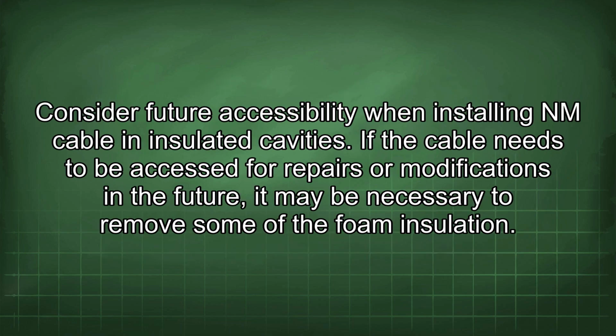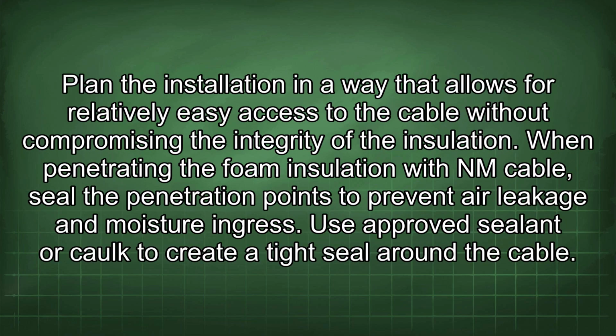Consider future accessibility when installing NM cable in insulated cavities. If the cable needs to be accessed for repairs or modifications in the future, it may be necessary to remove some of the foam insulation. Plan the installation in a way that allows for relatively easy access to the cable without compromising the integrity of the insulation. When penetrating the foam insulation with NM cable, seal the penetration points to prevent air leakage and moisture ingress. Use approved sealant or caulk to create a tight seal around the cable.